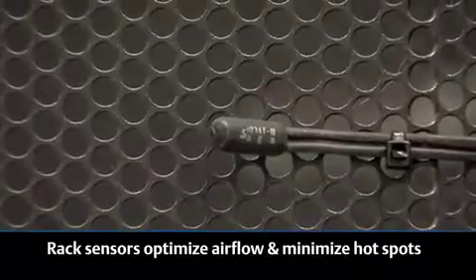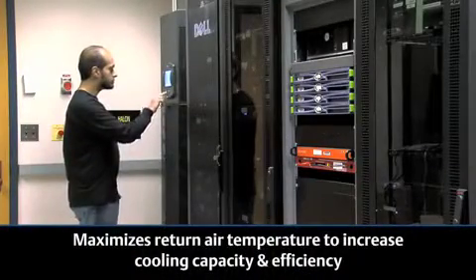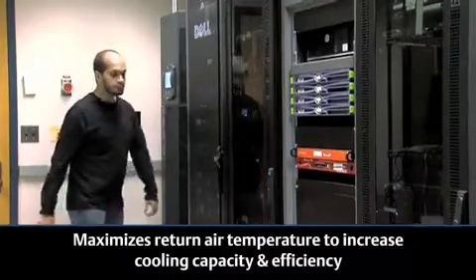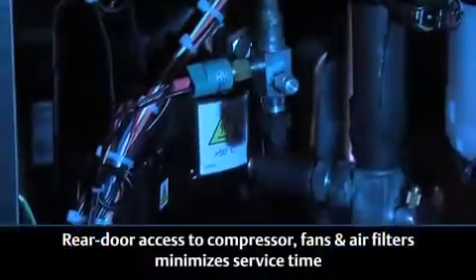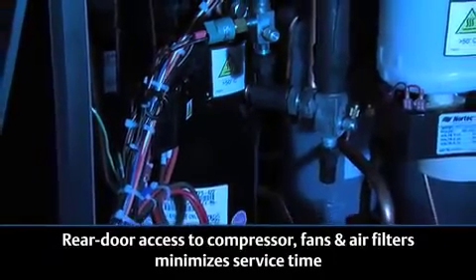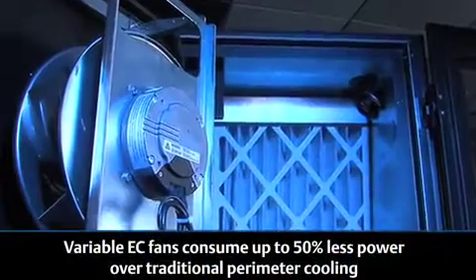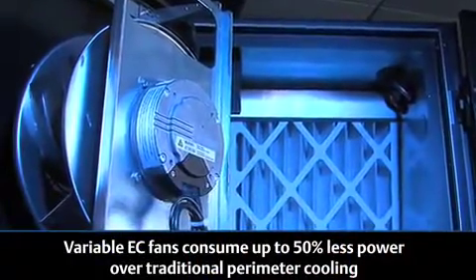It allows us to direct the airflow directly towards hot units, and also allows us to easily add capacity by just adding another row. A row-based solution like the Liebert CRV offers a great deal of additional efficiency over a room-based cooling system — it's cooling only where we need cold air, essentially the intakes of our racks. The Liebert CRV's digital scroll compressor runs essentially as much as it's needed, meaning the air coming out of our cooling unit is as cool as it needs to be at that moment. The unit doesn't need to struggle to cool the room, and the air is comfortable for our data center techs. The Liebert CRV's EC fans run at the speed necessary, and the noise signature is a lot better than our old unit.